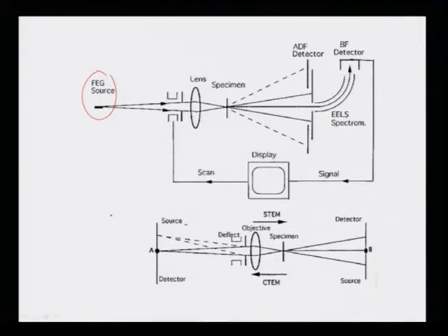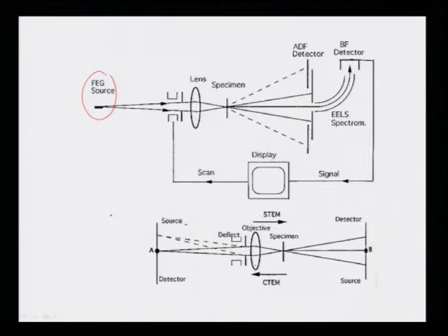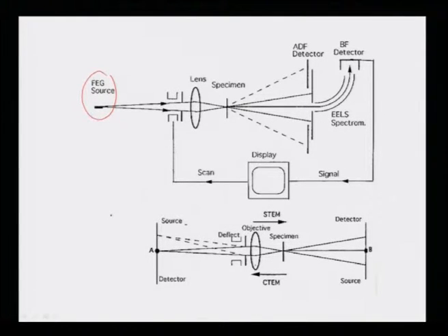One can use different detectors below the specimen to obtain images using either the transmitted or diffracted beams. The beam is scanned over the sample by a deflector — similar to a scanning electron microscope — and falls on the objective lens, which focuses and demagnifies it to a very small convergent beam on the specimen, producing different kinds of information.